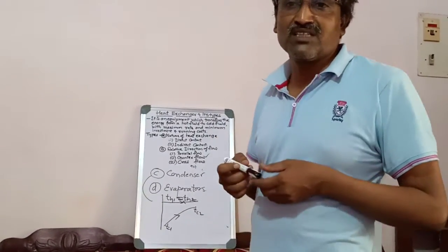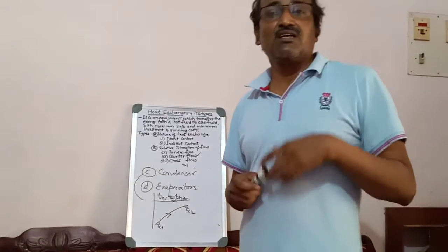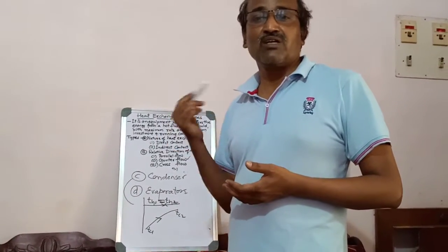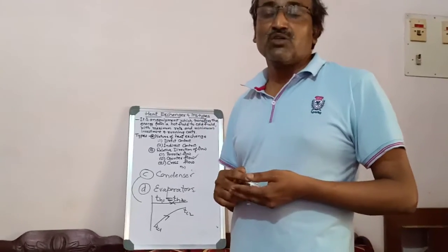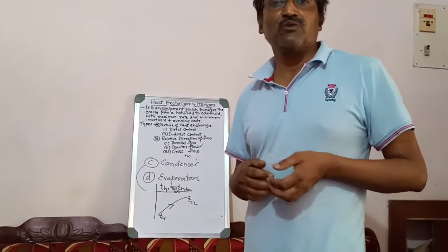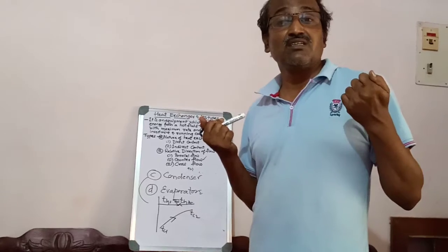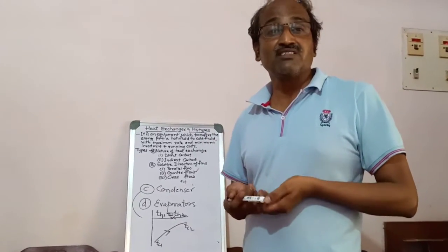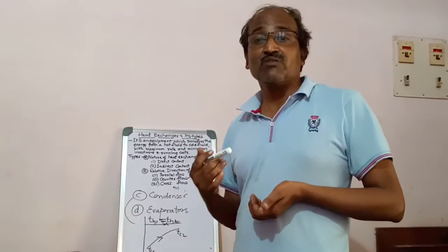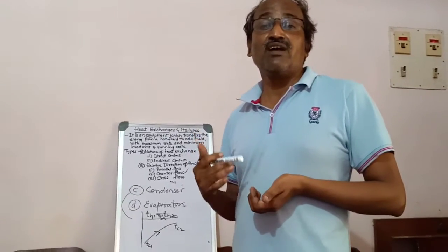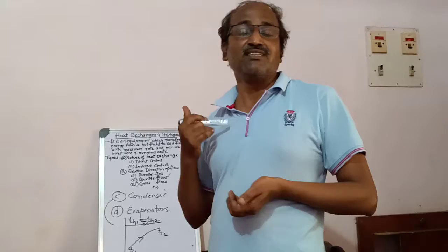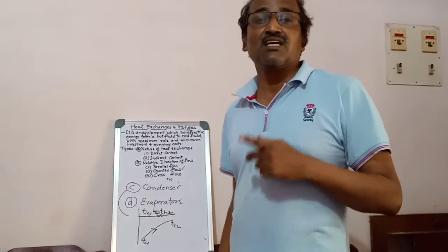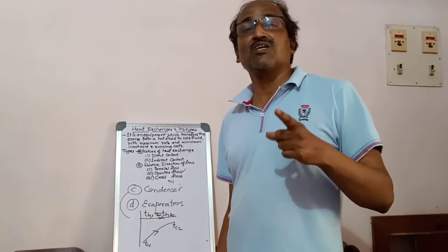Usually in the examination or in practical labs, there is always a viva question: between parallel flow and counter flow, which one is superior? You will tell that counter flow is superior to parallel flow. Why is it superior? Because the temperature difference is higher in counter flow. Why is the temperature difference higher? Because the cold fluid always finds the higher temperature of the hot fluid. That is the basic reason. The cold fluid in the counter flow heat exchanger always finds the high temperature of the hot fluid.